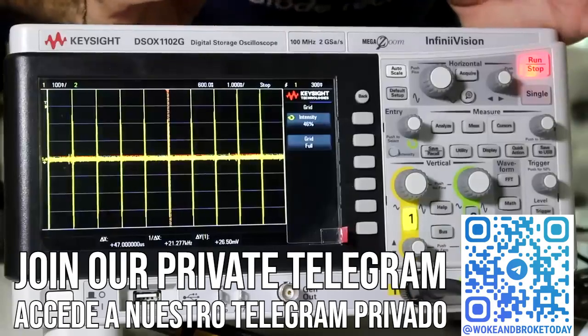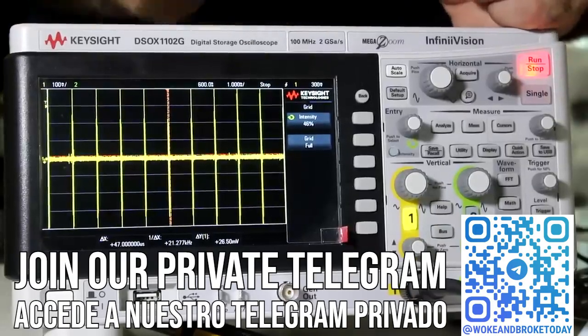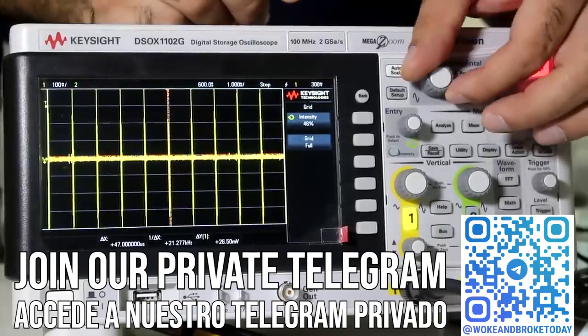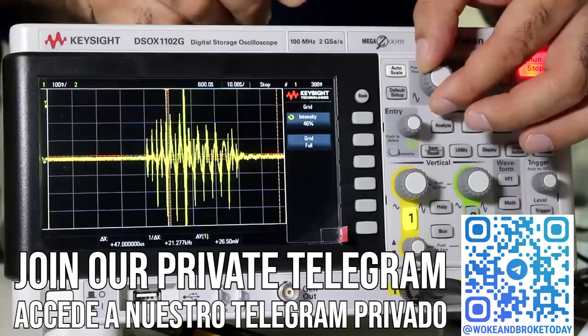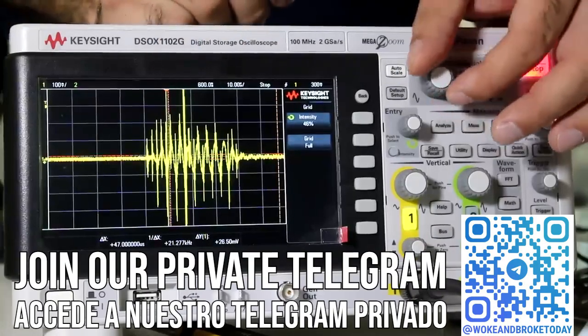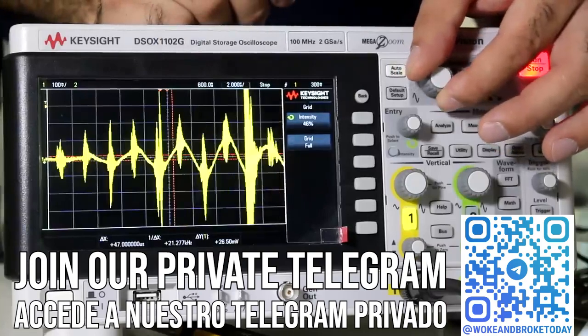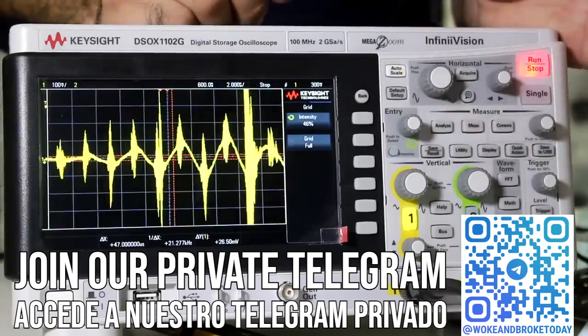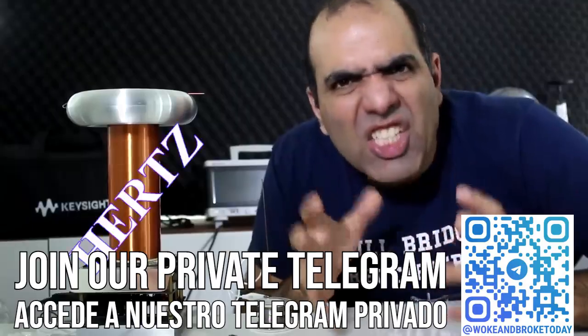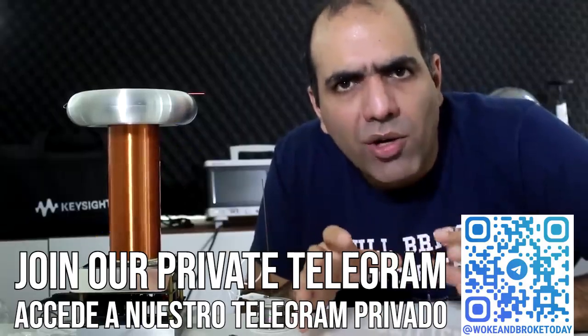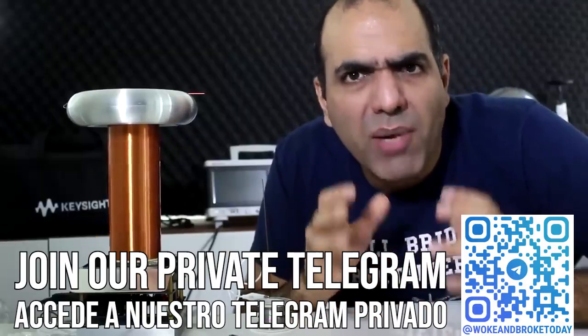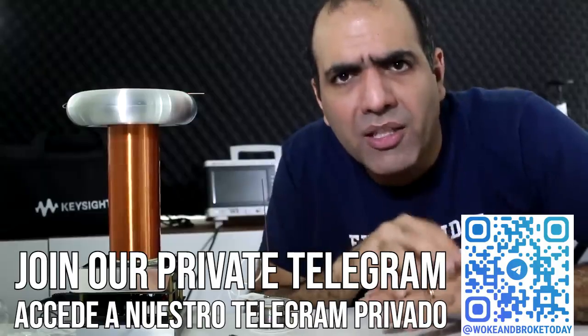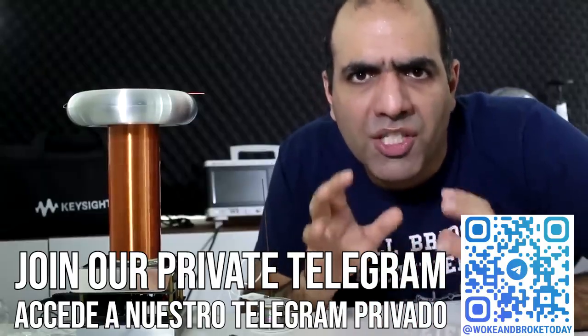So what we captured is that at 1 kHz setting we have a pulse every 1 millisecond, and the pulse duration at maximum setting is around 40 microseconds, and the resonance frequency is around 300 kHz. So that's why this arc hurts so much. See, in my old Tesla coil I had a continuous stream of 1 MHz signal which would not penetrate inside the body due to conductor skin effect.